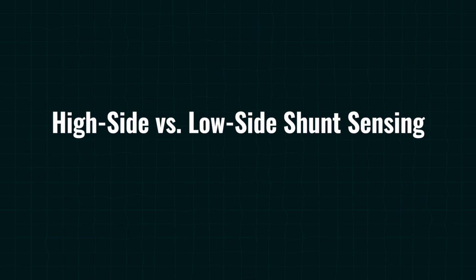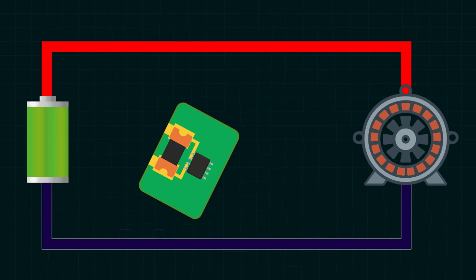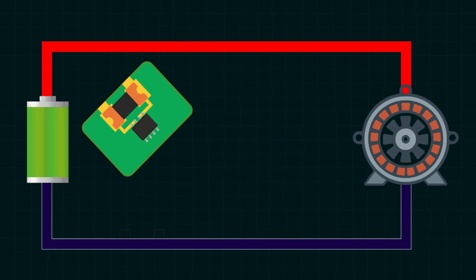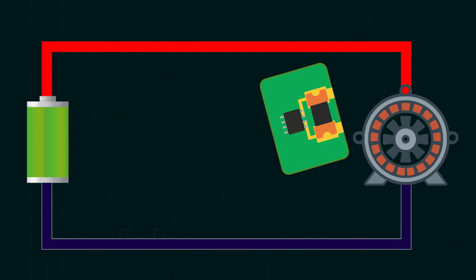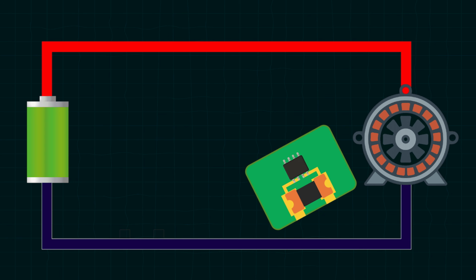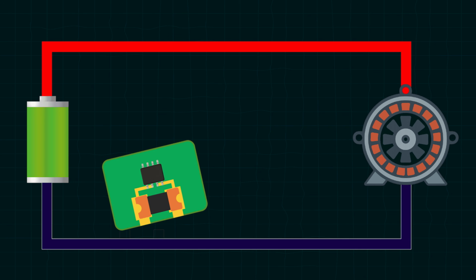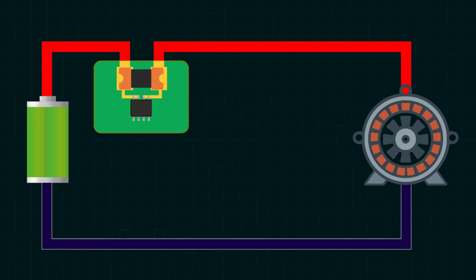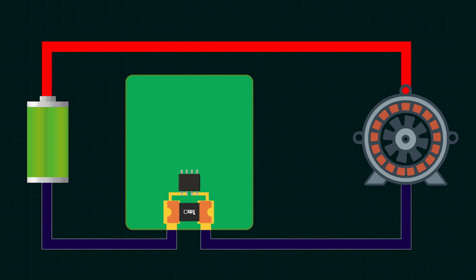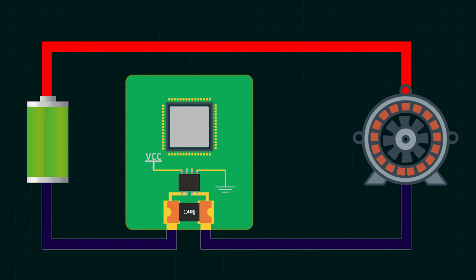High side versus low side shunt sensing. Now, there's one important design decision we have to make when using a shunt-based current sensor, which is where should we place the shunt? There are two common options, low side sensing and high side sensing. Let's start with low side sensing. In this setup, the shunt resistor is placed in the return path, typically between the load and ground. It makes the current sense amplifier operate at a common mode voltage close to zero, which is easy to work with. Most op-amps and ADCs are designed to handle ground-referenced signals.